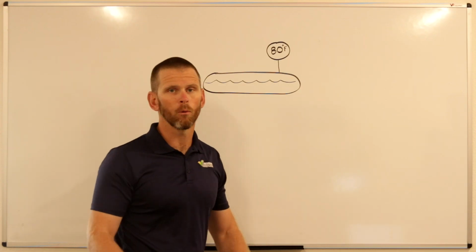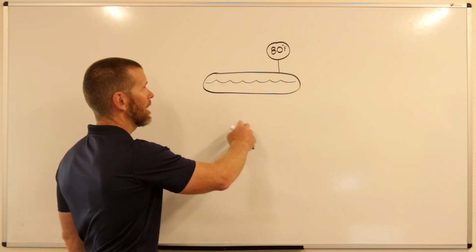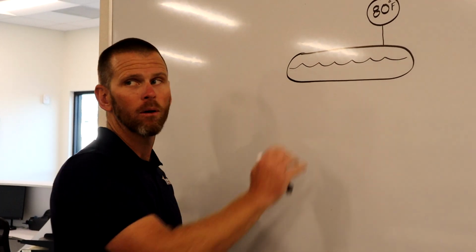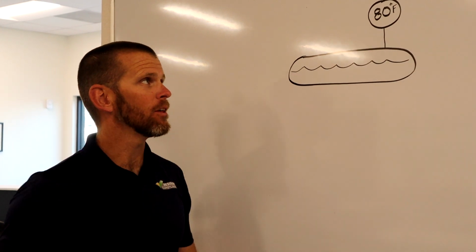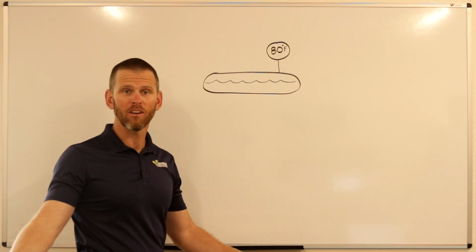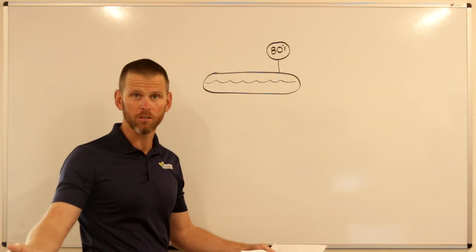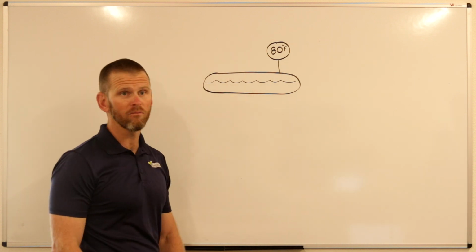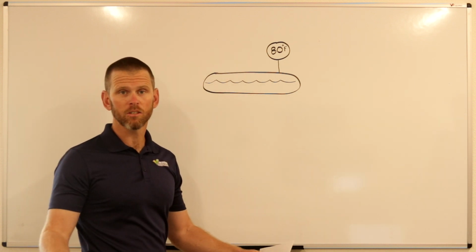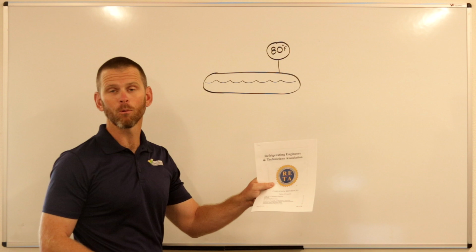Okay, in this first example, we have a high pressure receiver that has liquid and vapor ammonia in it, and the temperature of the ammonia is 80 degrees, and we're asked to find the corresponding saturation pressure.